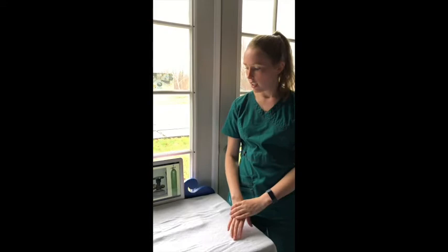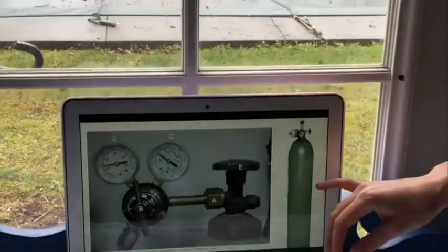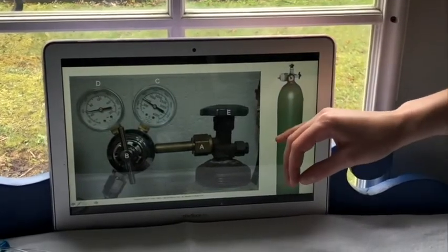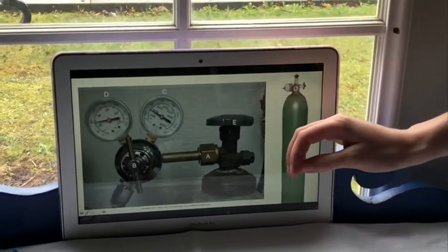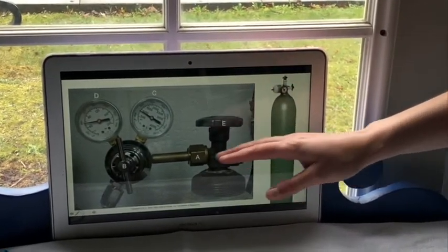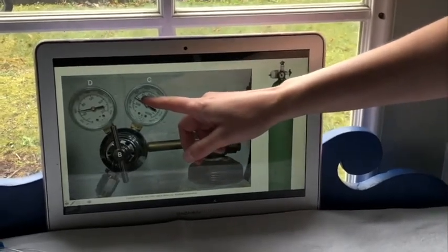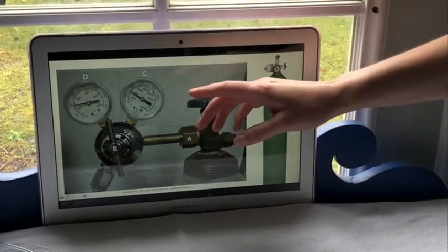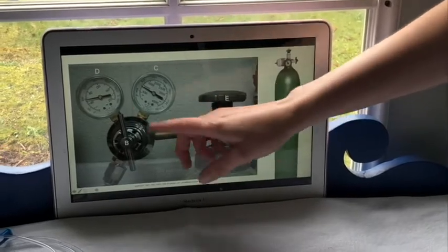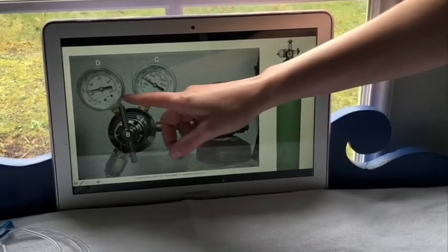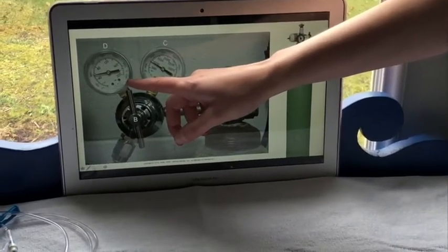Okay, so we're going to set up our anesthesia machine, and we're using a rebreathing circuit because Sally is greater than 15 pounds or 7 kgs. So the first step to setting up our anesthesia machine is turning the oxygen on. So we have our oxygen tank, we're going to turn it on. We need to make sure that the PSI in the tank is greater than 500, which it is. It's about 900. A full tank would be 2200 PSI. And then we need to make sure our regulator is set correctly at around 50 PSI.